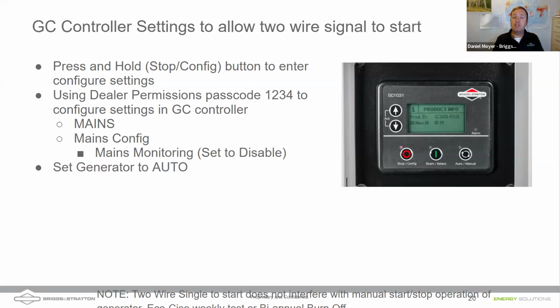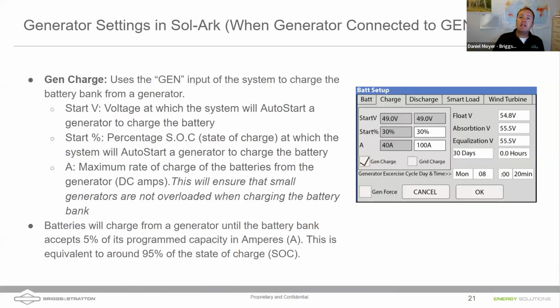One adjustment we need to do is get into our generator, get into the controller, and disable what's known as mains monitoring, so that the generator, if it sees the two-wire signal start, will still start up and run accordingly. Now, there are some settings that we need to change or at least pay attention to in the Sol-Ark as well. And I will just say this, there's a number of settings that need to be adjusted in the Sol-Ark programming.